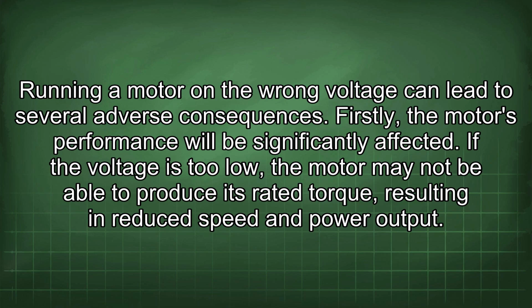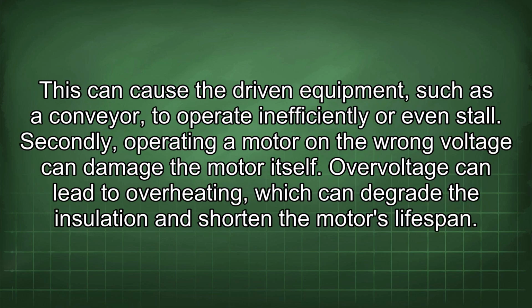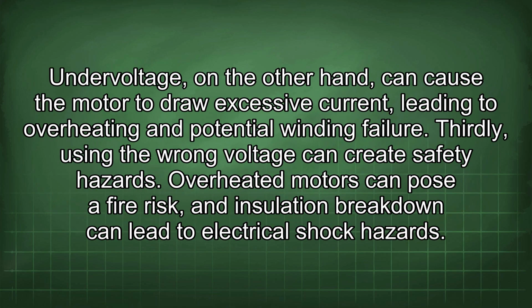If the voltage is too low, the motor may not be able to produce its rated torque, resulting in reduced speed and power output. This can cause the driven equipment, such as a conveyor, to operate inefficiently or even stall. Secondly, operating a motor on the wrong voltage can damage the motor itself. Overvoltage can lead to overheating, which can degrade the insulation and shorten the motor's lifespan. Undervoltage, on the other hand, can cause the motor to draw excessive current, leading to overheating and potential winding failure.